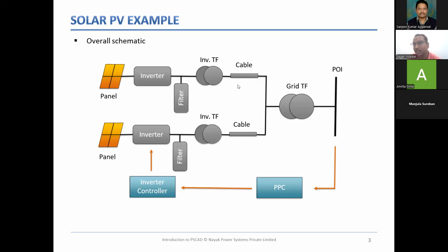Whereas the grid is at hundreds of kVs of voltage, for example, 132 kV, 400 kV. So we require something called an inverter transformer connected to a bank of inverters that will elevate that voltage from 0.69 kV to, let's say, 33 kV. Now, once this voltage is stepped up to 33 kV, as I said, there's not a single panel or two panels, there are hundreds of panels. So we require something called a collector system. It's called a cable collector system, which can have hundreds of cables collecting power from all these independent converters and clubbing it together, collecting it into one place.